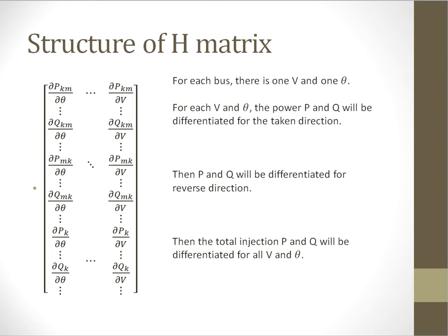Hello everyone, welcome back to power system state estimation. Let's start with the Jacobian matrix. The Jacobian matrix is denoted with H. In the Jacobian matrix, the equations of all measurements are differentiated with respect to all state variables. If there are m measurements and n states, the number of rows will be m and the number of columns will be n.